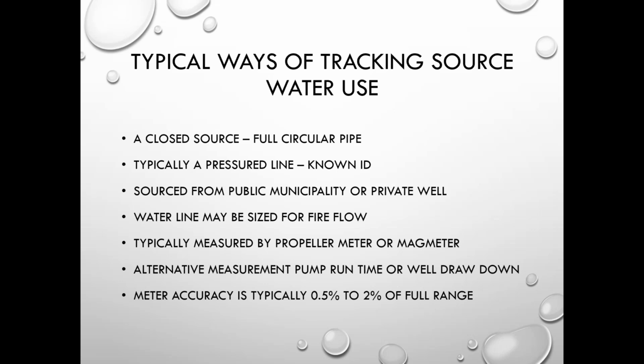The water line many times is sized for fire flow, and when you have to size a flow meter for fire flow, you're generally going to be running at the very low end of what the flow meters can run at. So we find that the fire flow requirement requires that the flow meter read very high, say 3,300 gallons a minute. But the flow meter's low end is at 330, and most of the time they're running at say 400 or 500. So when you size a flow meter for fire flow, you have to take into consideration that the normal flow is going to be on the low end, and it could provide some inaccuracies when you're running at a low velocity. And I'll go over that in some later slides.